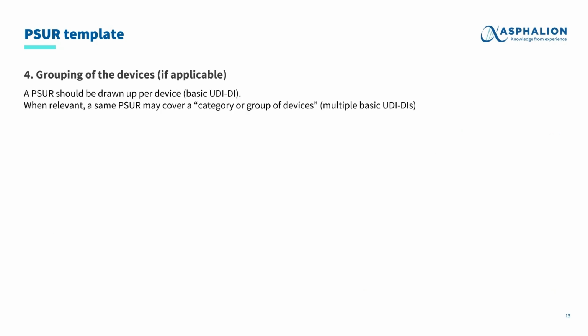After that section, we will have to include a justification for grouping of the devices, if applicable. It is worth mentioning that according to the medical device regulation, a PSUR should be drawn up per device. That means that each PSUR should cover one basic UDI. However, in some cases, manufacturers could consider the possibility of including in the same PSUR a category or group of devices, which means that multiple basic UDIs will be included in one PSUR.